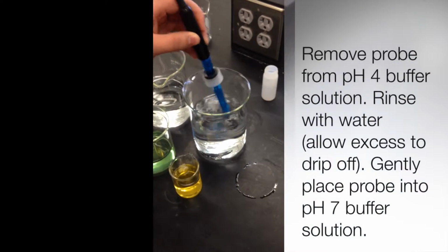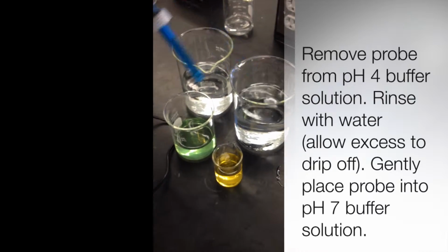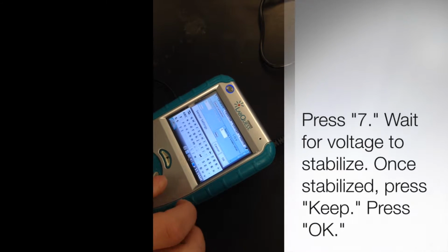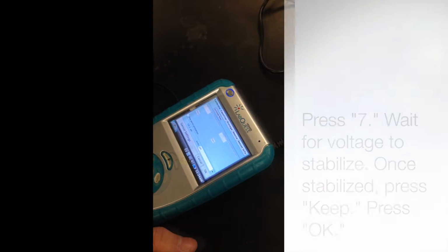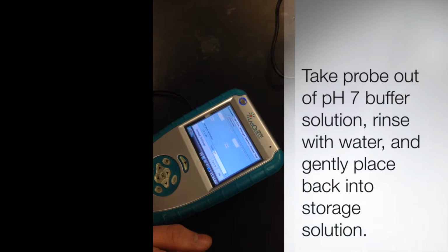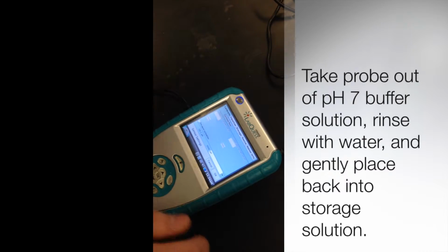Then we're going to take the probe out of the pH 4 buffer and rinse it off with the H2O, and then place it in the pH 7 buffer. It's stabilized at 1.7, so we're going to keep it, and then rinse it off with water, put it back in the storage solution, and then we're going to press OK.